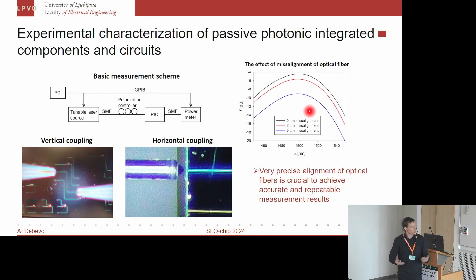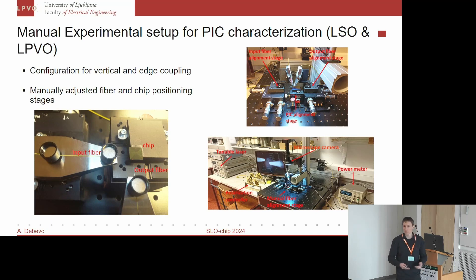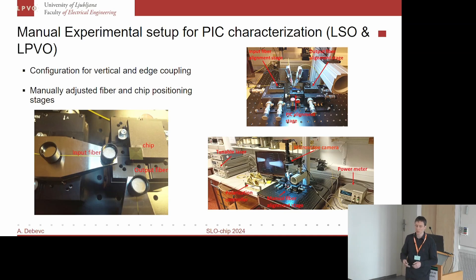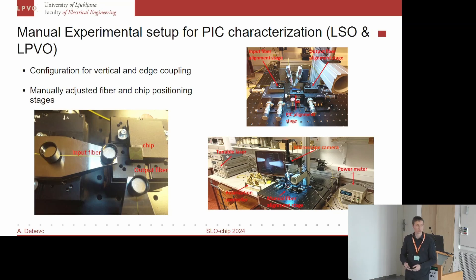This is our first measurement setup, already presented at last year's conference. It allows for vertical as well as edge coupling of photonic chips and consists of manually adjusted stages for fiber and chip positioning. We can position the fibers very accurately and achieve good measurement results. However, the alignment process is quite meticulous and demanding for the user, and it is sometimes difficult to achieve good repeatability.